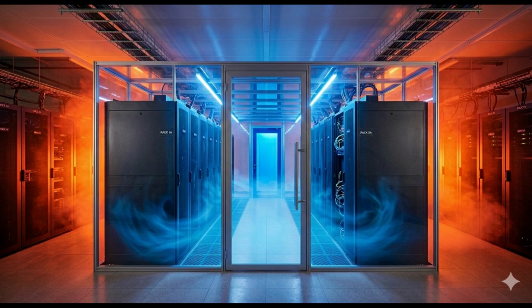How does a cold aisle become a vacuum? It happens when the volume of air being supplied by the cooling units drops below the volume of air being demanded by the server fans. The cooling airflow is less than the IT airflow demand. So the servers are sucking harder than the room can supply. Exactly. And because fluids move from high to low pressure, that vacuum in the cold aisle will violently suck warm air backward from the hot aisle through any tiny gap or unsealed opening in the racks. We call it recirculation. Well, that's a disaster.